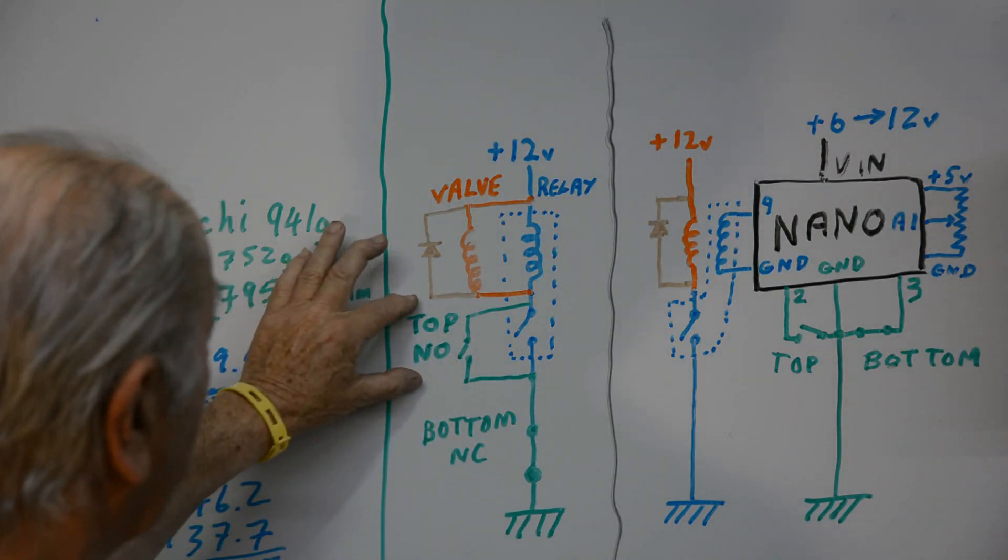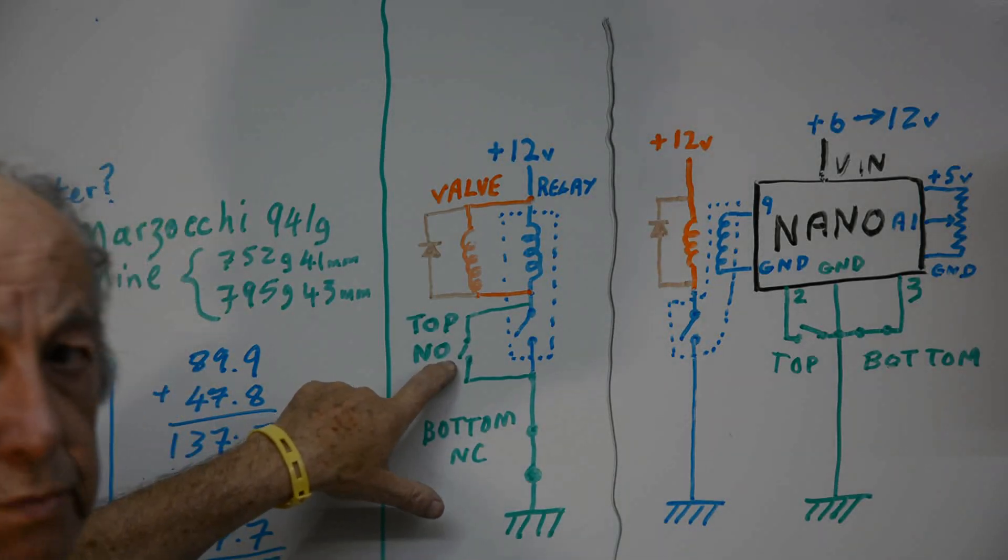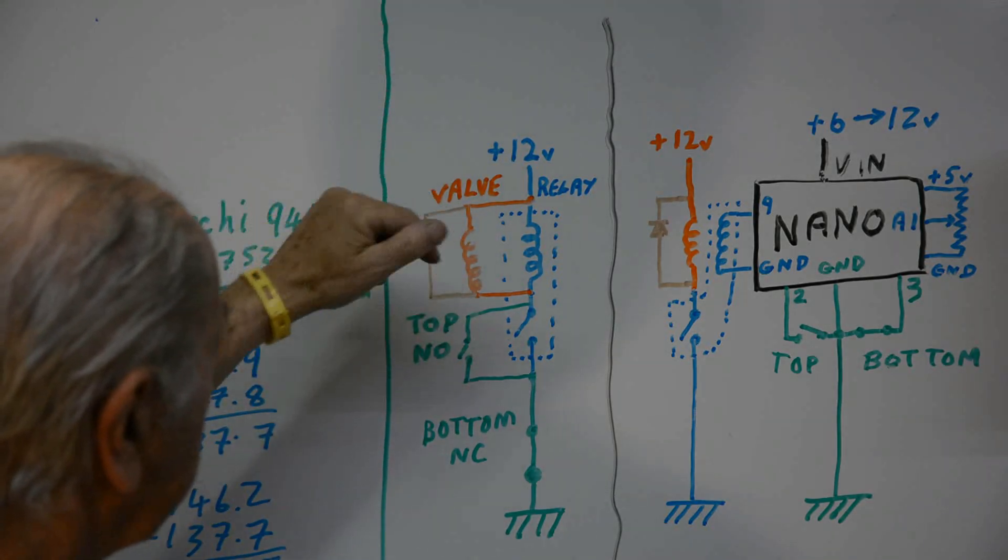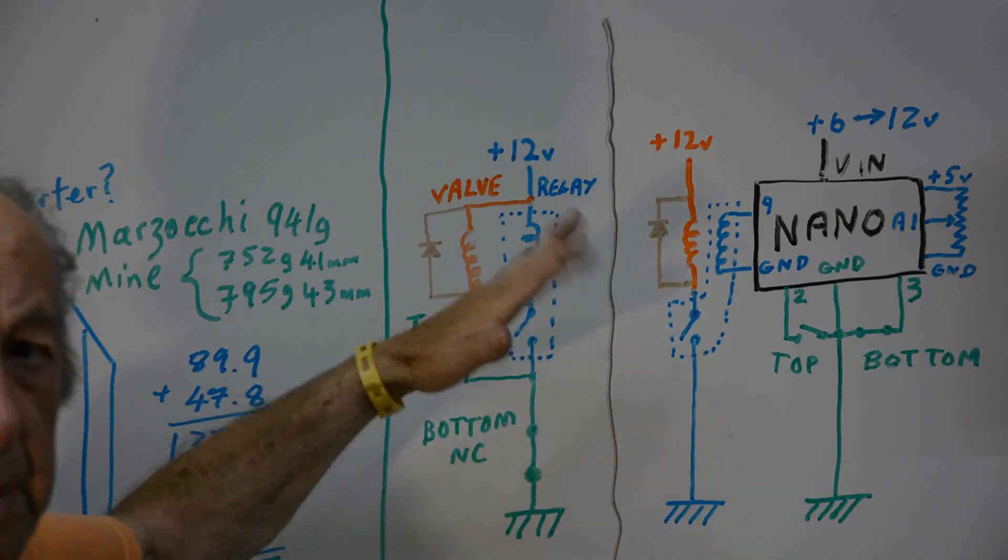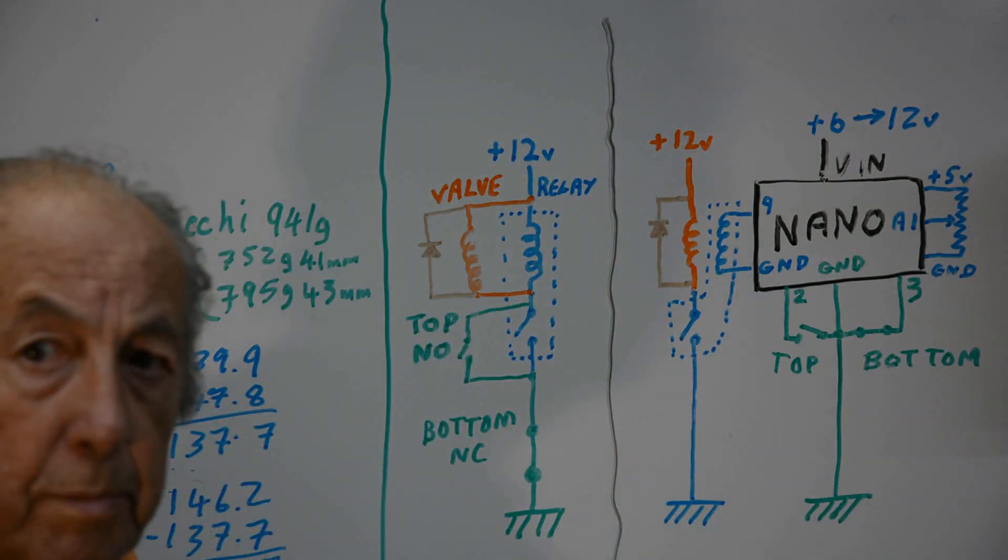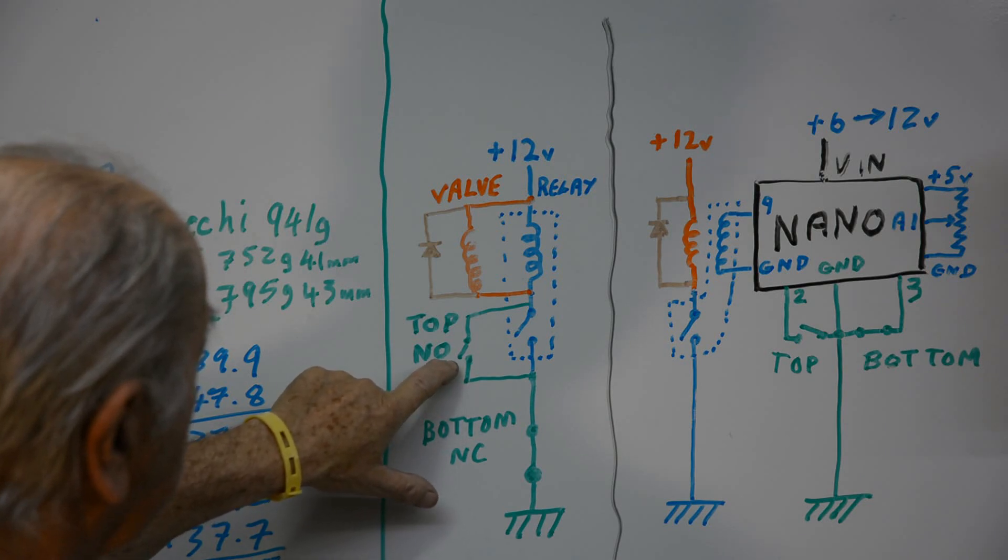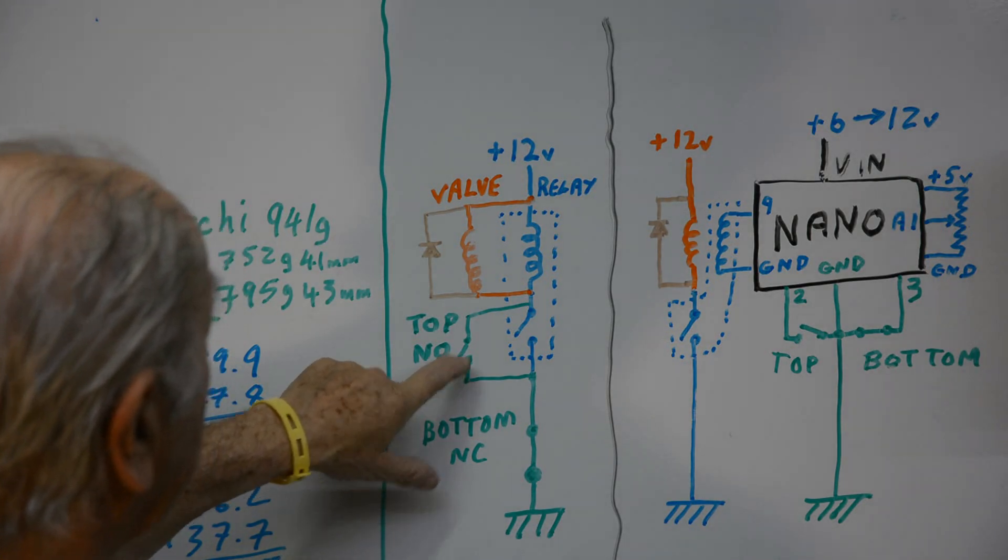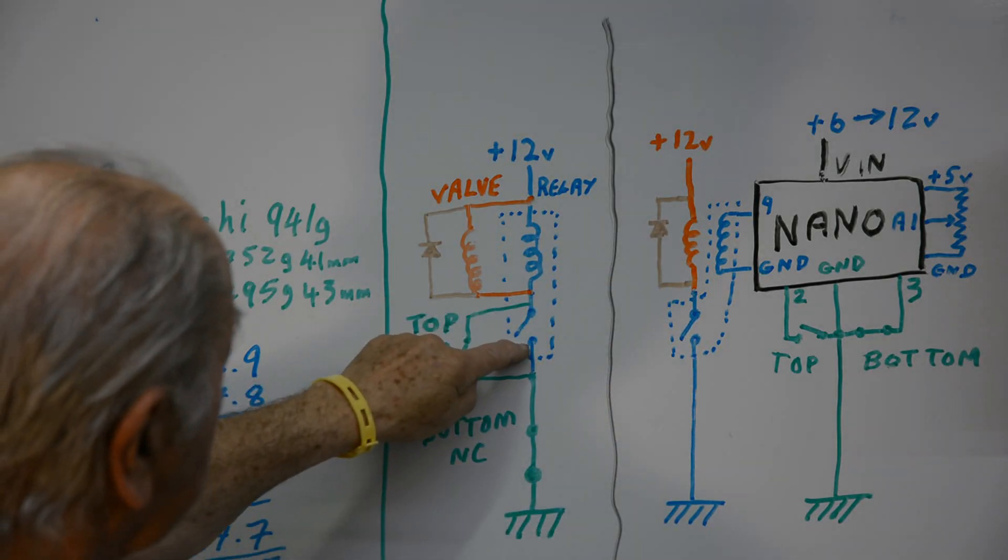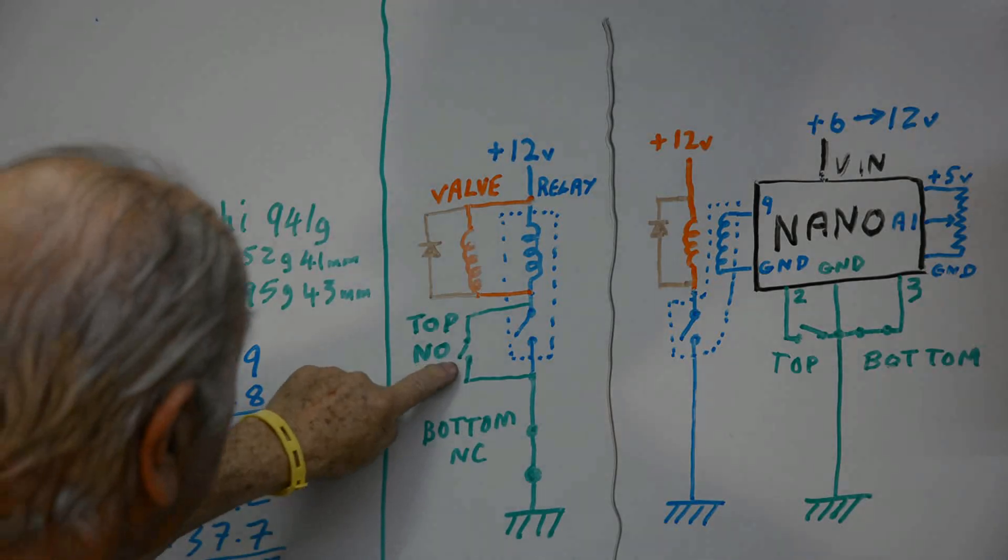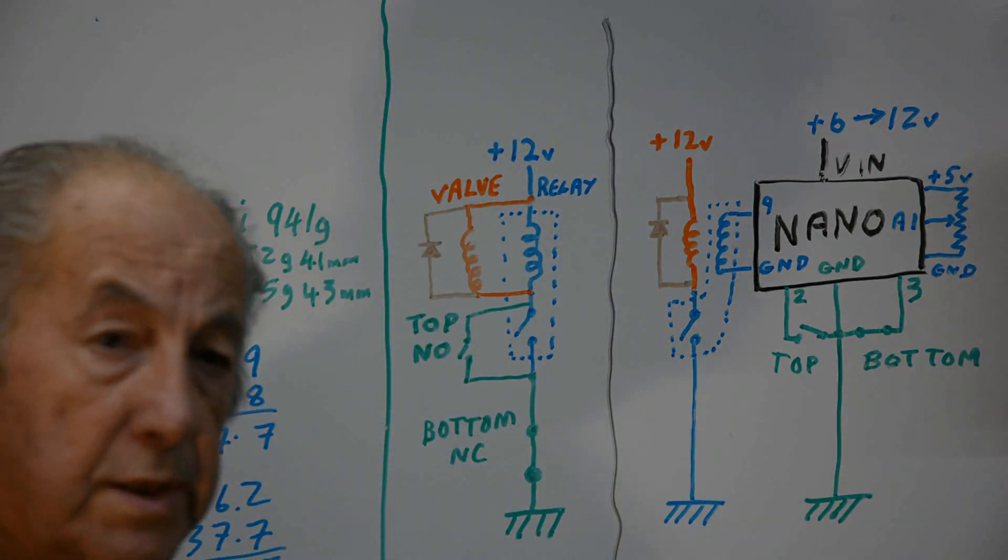Now if we just had that without the relay what would happen is as the ram was at the top it would close this switch so the ram would start moving down but then the switch would open almost straight away and so the ram would go up again. So the ram would just dither about like this at the top of its stroke. What happens with the latching relay is when the ram is at the top and it closes this contact, as well as powering the solenoid valve it powers the relay but its own contacts are then closed. So when this one opens this is still closed and so it maintains the current flow through the solenoid valve.